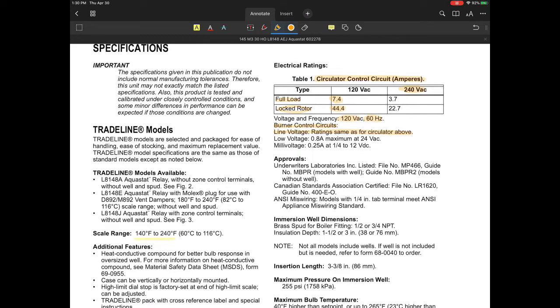The line voltage for the burner circuit is another important one here. They're identifying the line voltage rating as the same as the circulator circuit above. Here's why I want to bring that to your attention. A lot of times with the line voltage for the burner control circuit, let's say you have a fan assisted boiler, so you might have a cast iron boiler that has an inducer fan. They will often have the burner circuit energize the inducer motor and get that running, and then once the pressure switch makes, the pressure switch is the controlling circuit that allows the burner circuit to energize, let's say, the ignition module and things like that. So they do have some alternatives there, and again, you have to watch that.